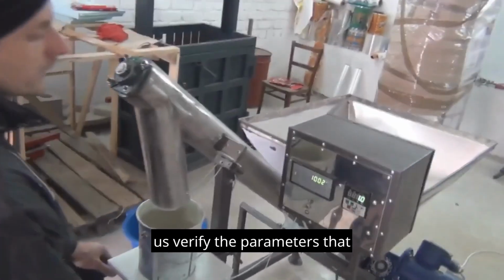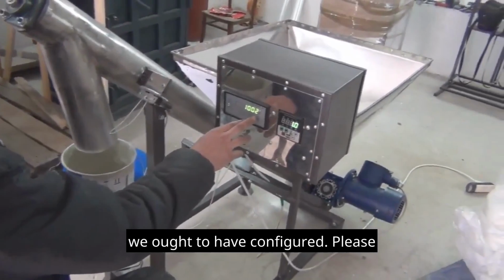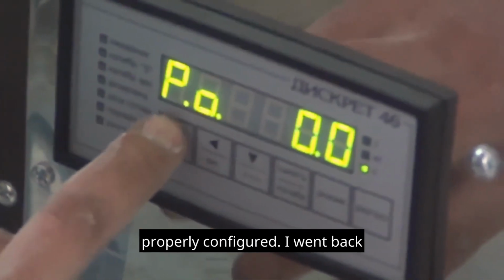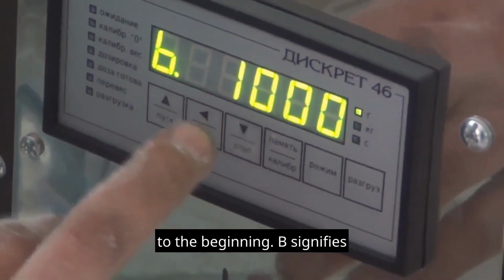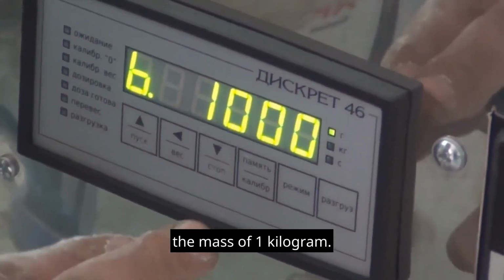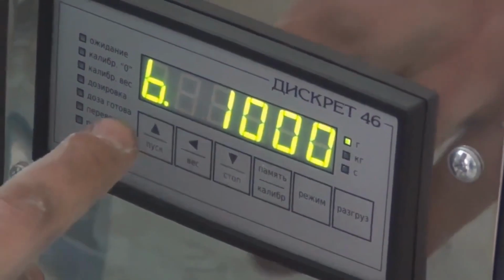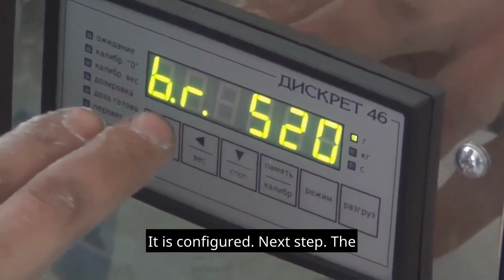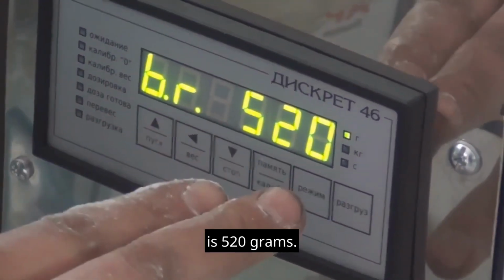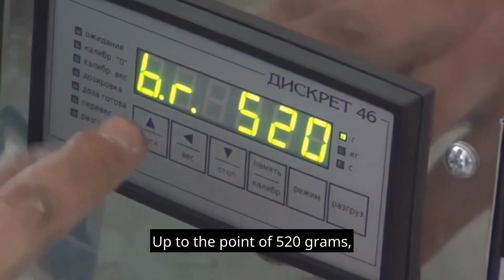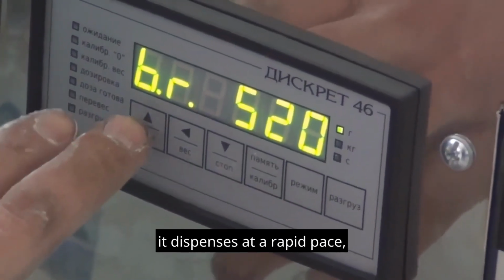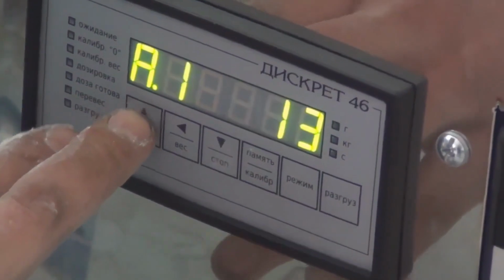Let us verify the parameters that we ought to have configured. Please press the mode button. We should have these parameters properly configured. I went back to the beginning. B signifies the mass of 1 kilogram. It is configured. Next step. The mass of the approximate dosage is 520 grams. Up to the point of 520 grams, it dispenses at a rapid pace, and subsequently it gradually adds more.